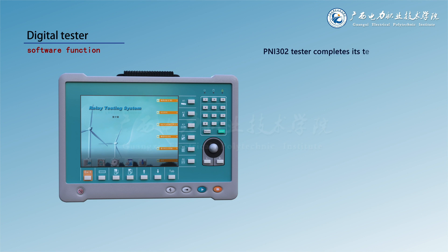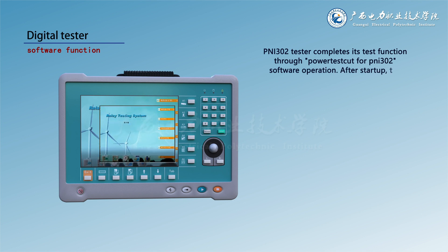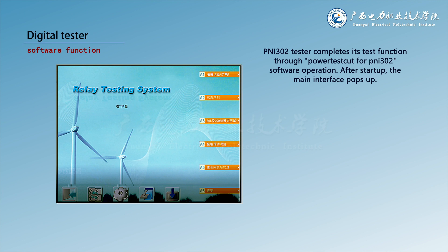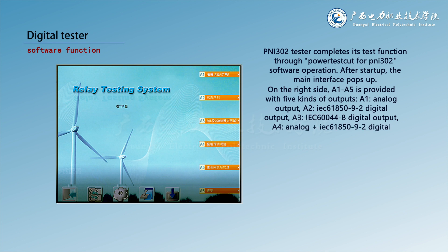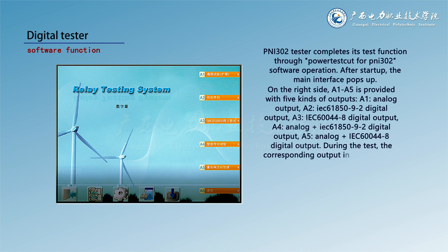The PNI302 tester completes its test functions through the powertestcut for PNI302 software. After startup, the main interface pops up. On the right side, A1 through A5 provides five kinds of outputs: A1 analog output, A2 IEC 61850-9-2 digital output, A3 IEC 60044-8 digital output, A4 analog plus IEC 61850-9-2 digital output, and A5 analog plus IEC 60044-8 digital output. During the test, the corresponding output in A1 through A5 can be selected according to the input type of the equipment to be tested.